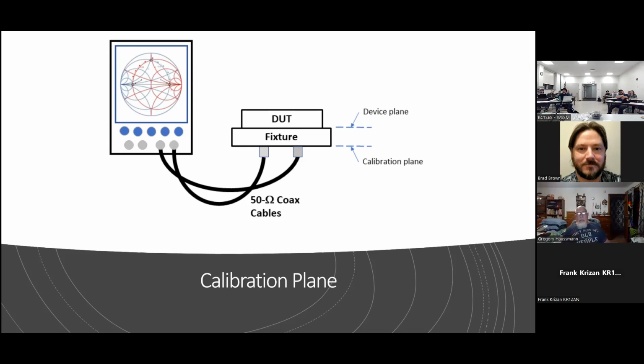One of the nice things about calibrating VNAs in general is you can calibrate, instead of calibrating to here as your reference plane, you can calibrate out to here. So what I do is I connect a little barrel and I put my calibration standard here. As a result, this entire cable might as well be inside of the VNA. It is invisible to you. The device will see it, it will interpret it, and it will remove it from its calculations. Where this can become helpful, say you have an antenna, you don't really care about how much loss you're incurring from your cable in this instance. You just want to know exactly what the SWR of your antenna is. As many people know, if you have a lossy cable feeding an antenna, your SWR is going to be better. It's going to seem to be better because that loss is happening and you're not getting that reflected power back. You could calibrate out that entire cable length, and then the only thing that you're actually measuring is the antenna itself.